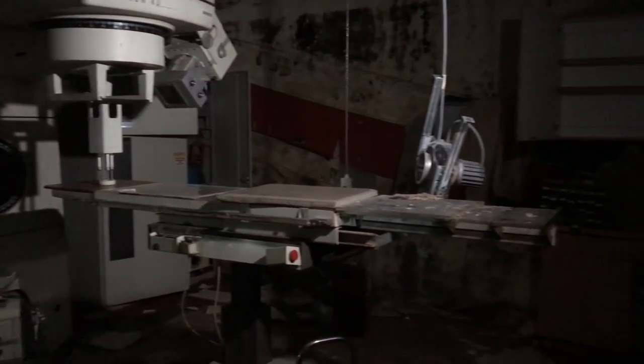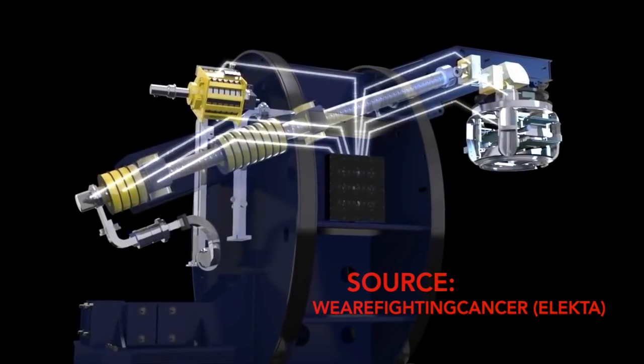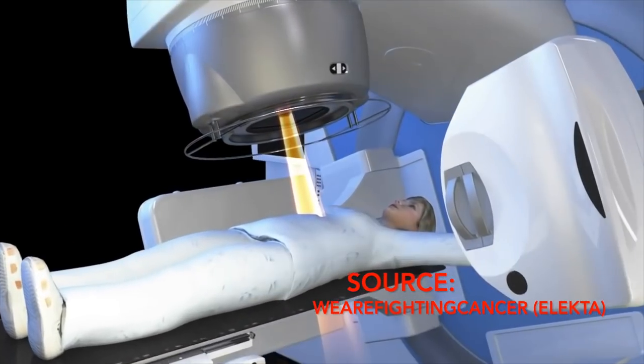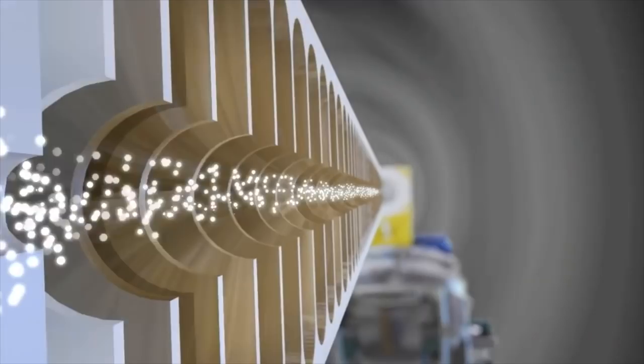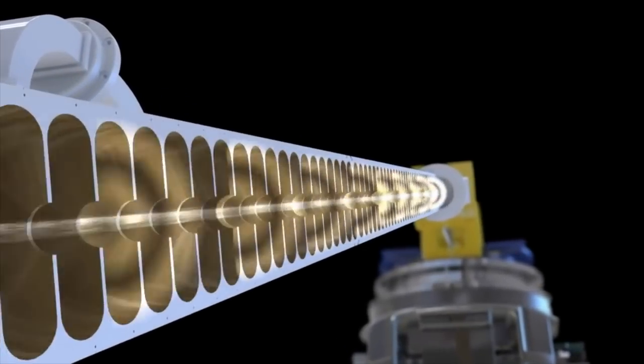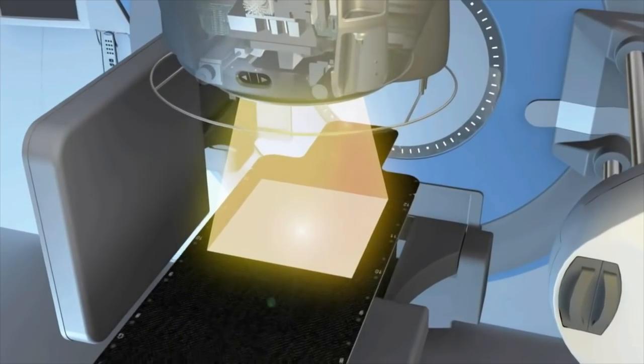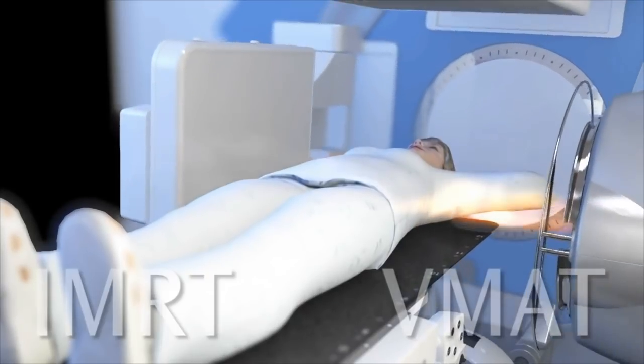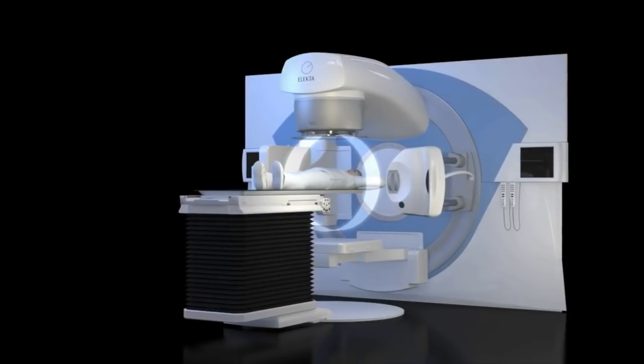There's one thing I did get right: it's an X-ray machine, but not an ordinary one. This particular type is used to kill cancer cells — it's called a linear accelerator, a type of particle accelerator. Electrons and radio waves are sent through a long tube; the radio waves accelerate the electrons close to the speed of light. After passing through several magnets to focus and direct the electrons, they hit a tungsten surface which produces X-rays directed onto the patient's affected area to kill cancer cells. Radiation therapy works because cancer cells are more vulnerable to radiation than normal healthy cells. These machines cost anywhere from $300,000 to $1.5 million.